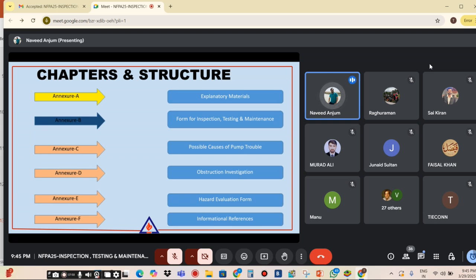In Annex A, there is some explanatory material. In Annex B, there are forms for inspection and testing. Some people asked me to provide a form for fire pump testing, or for testing any other fire and water related system. You can easily find the inspection and testing forms in Annex B. Besides this, some paid NFPA forms are also available on the NFPA website, which you can purchase and edit. They provide them in PDF form, but you can write all your observations during inspection in electronic form easily. Annex C covers possible causes of fire pump trouble, and Annex D covers obstruction investigations. Then there is the hazard evaluation form and so on.